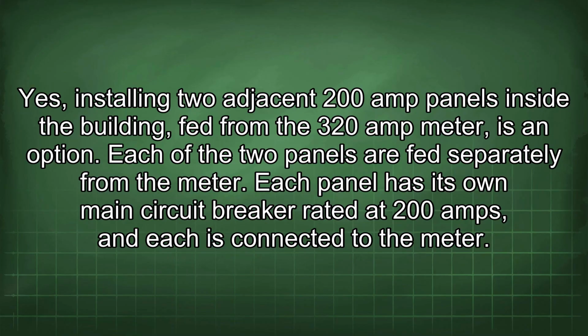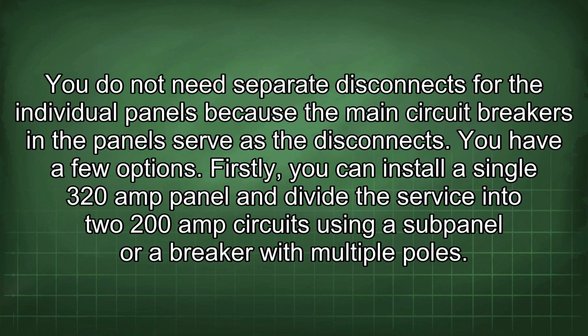Yes, installing two adjacent 200 amp panels inside the building, fed from the 320 amp meter, is an option. Each of the two panels is fed separately from the meter. Each panel has its own main circuit breaker rated at 200 amps, and each is connected to the meter. You do not need separate disconnects for the individual panels because the main circuit breakers in the panel serve as a disconnect. You have a few options.